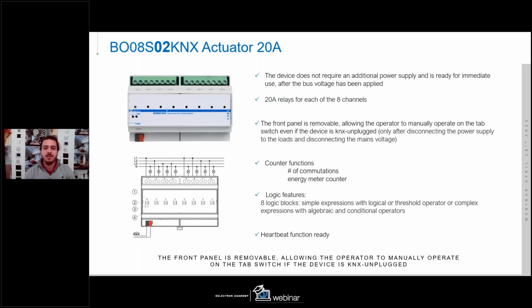Starting from the BO08S02 KNX version, that is a 20 amp relay with 8 channel output. This means, as we said before, that we can control up to 8 single lights for generic load or light management, plus a custom interlock. This means that we can enable interlock from 2 to 8 relays. Thanks to this device, you can connect more circuits with more load, of course, since we have a 20 amps relay, and also the peak current that we can support is more than a 16 amp relay.